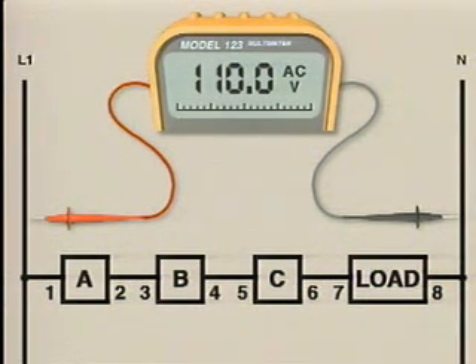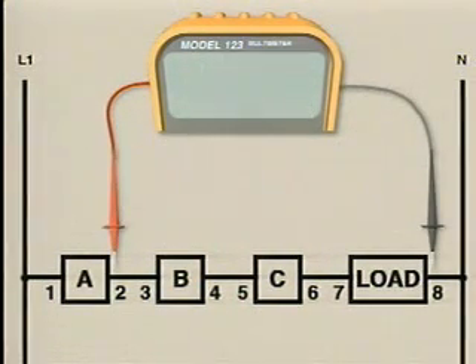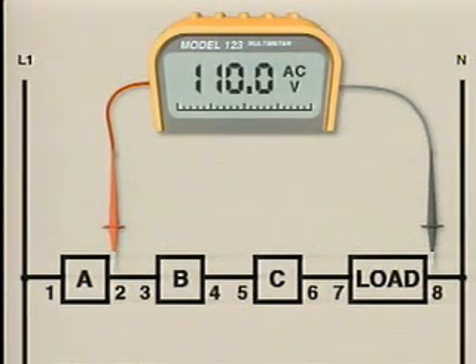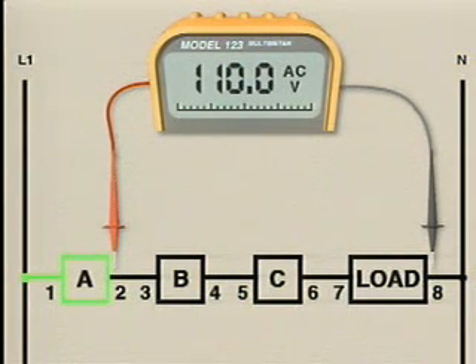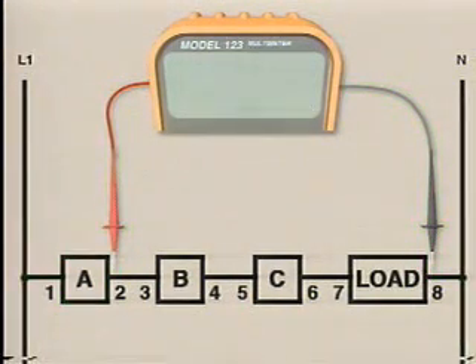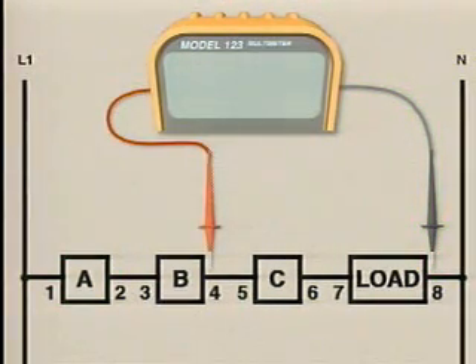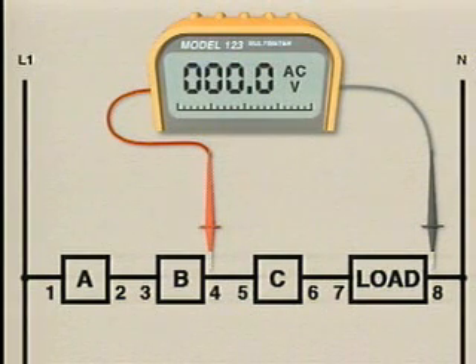It's a good practice to make sure that a circuit has voltage applied to it before you start checking the circuit's components. Generally speaking, whenever a voltage check indicates the presence of voltage, it means that there's a complete path through the circuit to the test instrument's probe, through the test instrument to its other probe, and back through the circuit. On the other hand, whenever a voltage check indicates 0 volts, it means that there could be an open in the circuit path that's being used for the check.